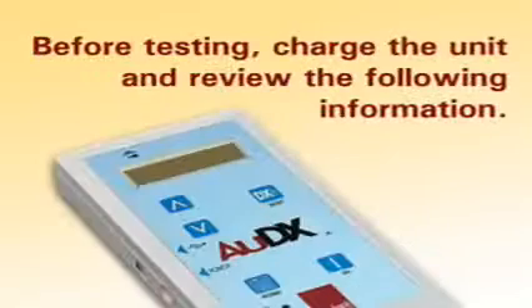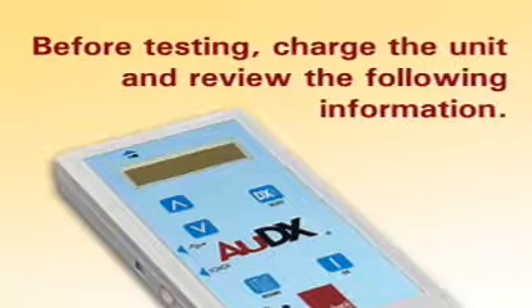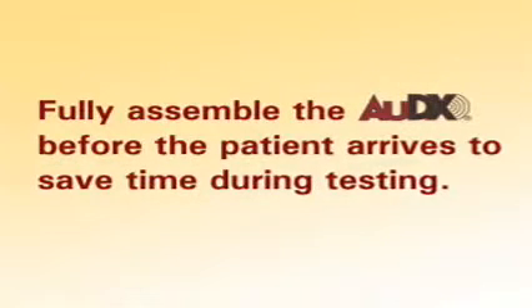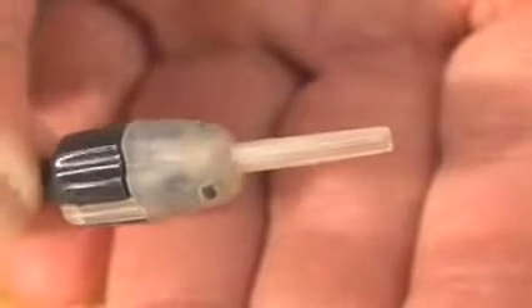Before you start testing, we recommend you charge the AuDX, preferably overnight, and review the following information and procedures. Fully assemble the AuDX before the patient arrives to save time during testing. Make sure the probe nozzle is securely attached to the probe body and clear of any debris. Then plug the probe cable into the AuDX unit.